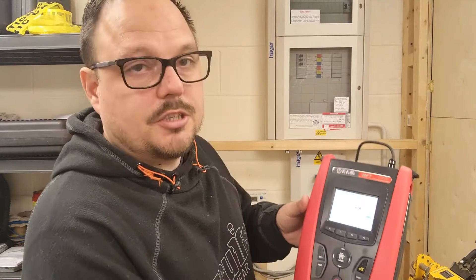Preps you a little bit time-wise on the EICR, and obviously if it's on the multifunction tester, you can do a little IR reading as well. So if I pop it around just the earthing conductor this time, so we're on just that one, and you can see it's measuring the 2 milliamps still. Pop that up. So this works in both ways.